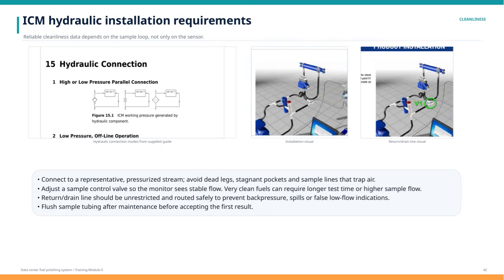The sample control valve should be adjusted to provide a stable flow to the monitor. Keep in mind that very clean fuels might actually require longer testing times or a higher sample flow to get accurate readings. The return or drain line is just as important. It needs to be unrestricted and routed in a way that prevents back pressure, spills, or any indication of low flow that isn't real. After any maintenance work, always flush the sample tubing thoroughly before taking the first measurement to avoid contamination. Overall, keeping these installation practices in mind will help you achieve reliable, consistent cleanliness data, which is critical for monitoring and maintaining fuel quality in your system.